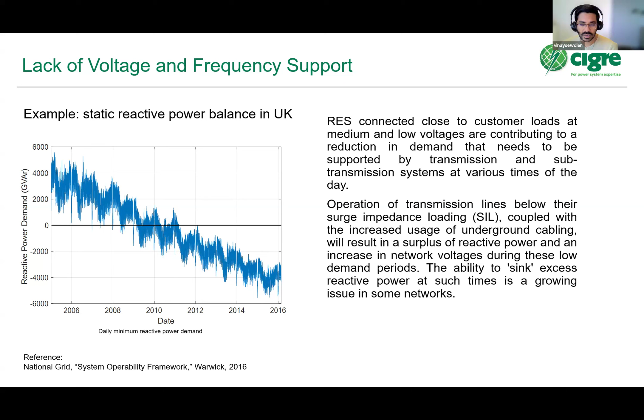One of the reasons is that when people install solar panels, the electrical loading on transmission lines reduces. As it reduces below something called surge impedance loading, your transmission lines change behavior from being inductive to being capacitive. That's one explanation. The other is that there's more and more capacitive demand in your power system, more power electronics essentially. So the way the power system needs to be managed is different. First it was inductive, now it's becoming more and more capacitive. This is a growing concern in the UK.